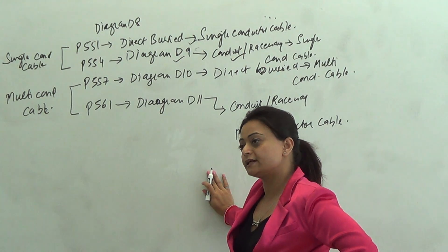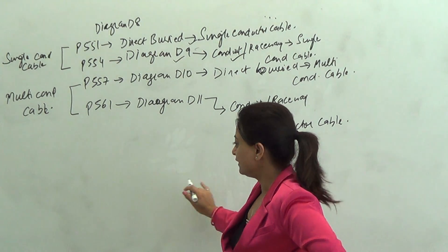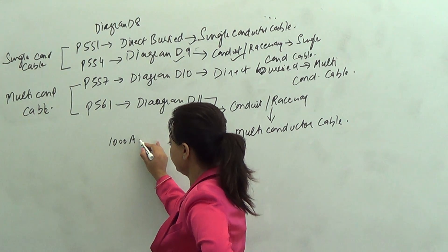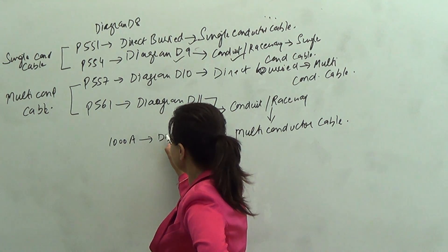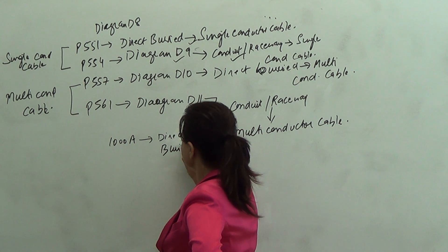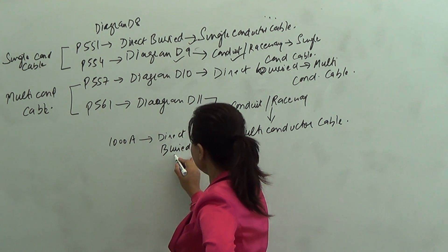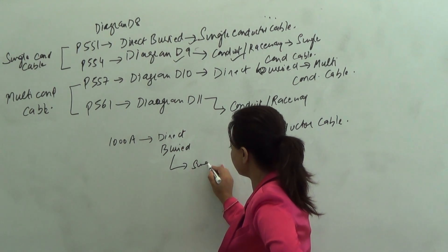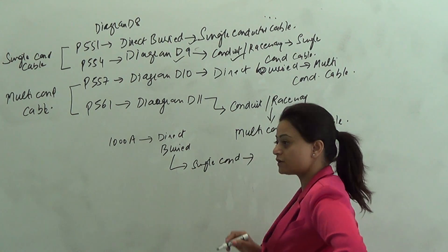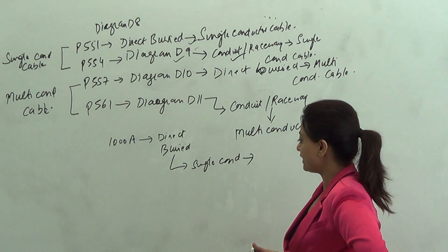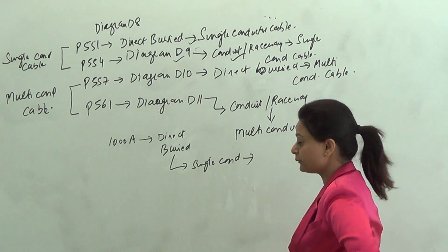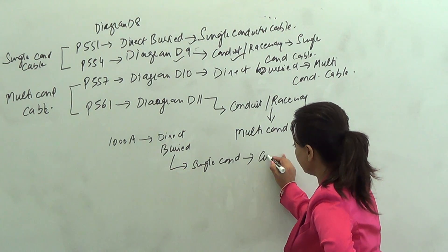So the question that I just asked you guys: I have 1000 amp service, I am installing the conductors underground, they are directly buried, and the conductor I am choosing is single conductor cable. All you had to do was go to the table right behind. I didn't say copper or aluminum — if I don't say copper or aluminum, that means copper.